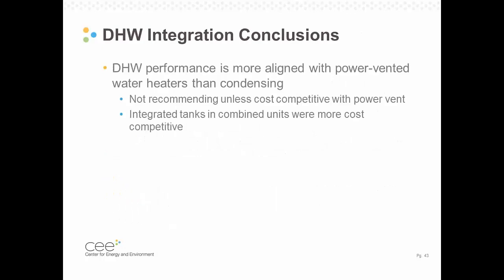As far as DHW integration, DHW performance for indirect water heaters definitely aligned more closely with power vented water heaters than condensing versions, and we didn't think they were quite cost effective unless they were cost competitive with power vented. So that cost would have to come down probably around $1,000 in order to be competitive. Likely the integrated tanks and potentially the single wall ones might be a little bit more cost competitive.